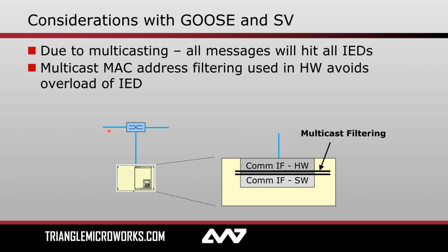In this case, every message is still being published everywhere on the network, but at this MAC address filtering layer on my device, I can very quickly and easily tell if a message is intended for me, because I know the MAC address of every GOOSE message and I know which ones I'm intended to subscribe to. So effectively this prevents the software layer from overloading because it's receiving too many GOOSE messages and trying to decide if they're relevant or not. Messages that aren't relevant are tossed out before they ever make it into the software layer.